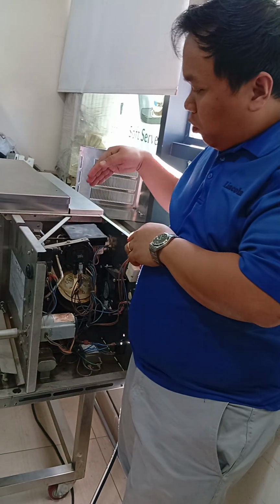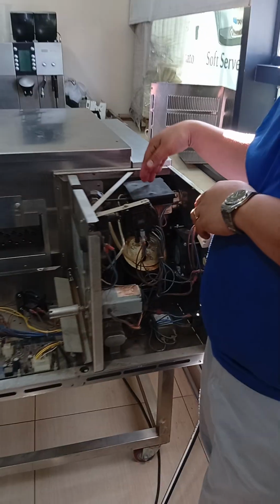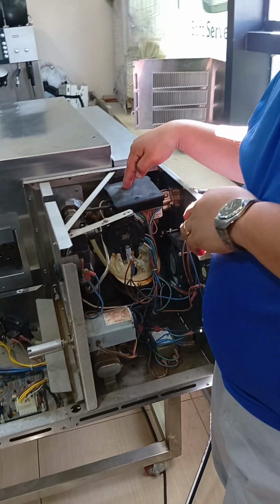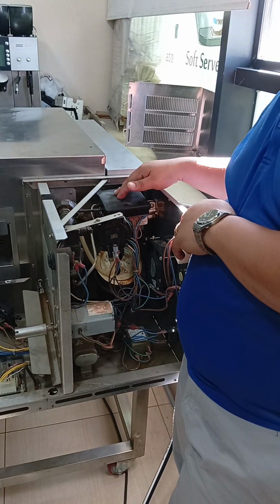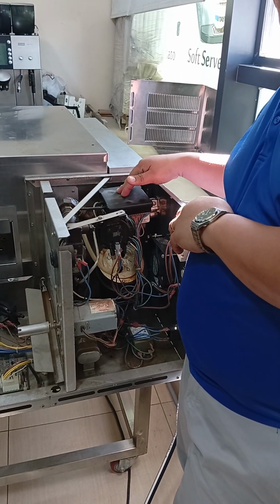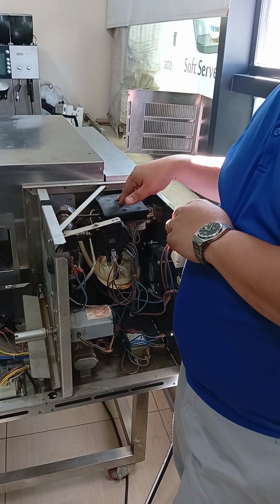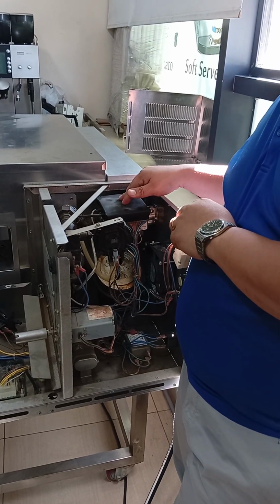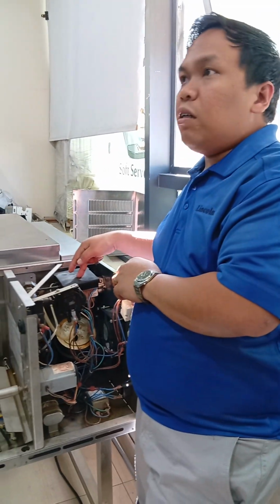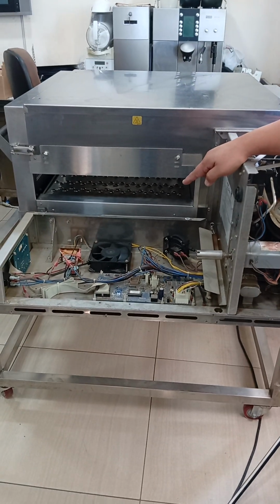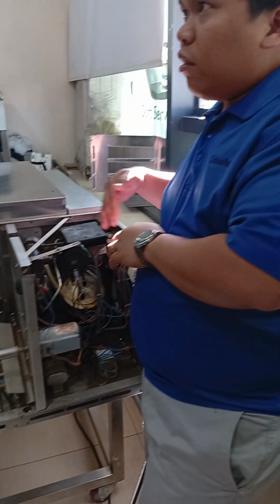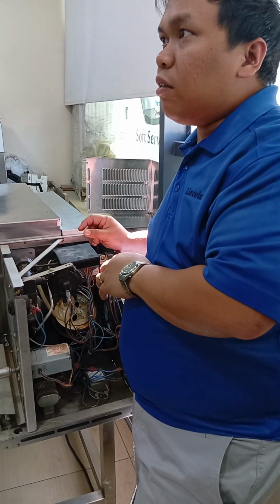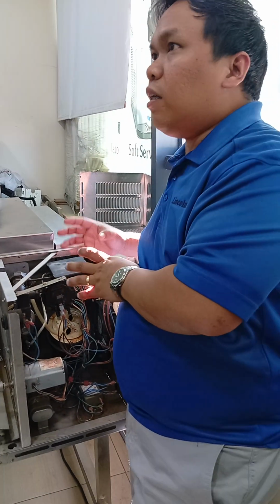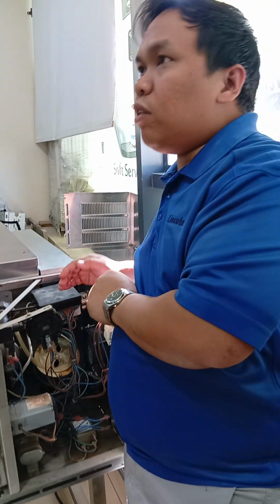And you need also to inform the customer, particularly for gas, they should have maintenance at least every 3 months, and every 6 months for electric. At that time you will inspect everything. What is included? Important is the cooling fan. Now you can see the internal of the compartment. If too much grease is coming, then you will inform them the extraction is not enough.